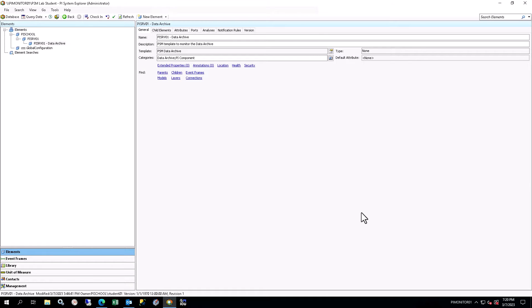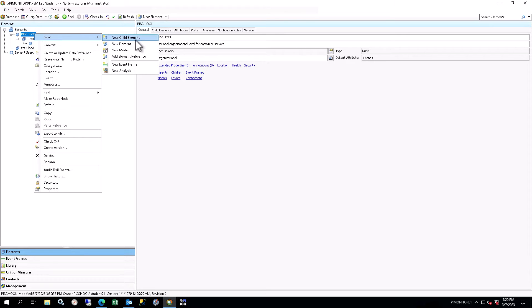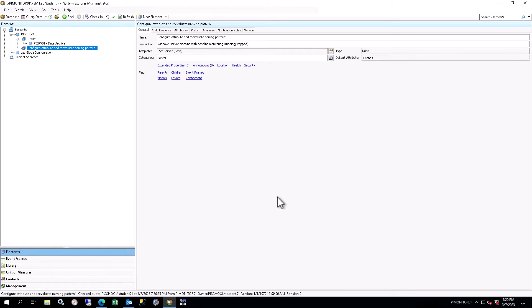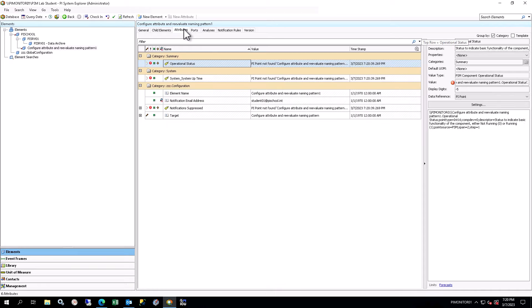In PI System Explorer, in the browser, right-click the PI School element in your database and select New, New Child Element. In the Choose Element Template window, ensure reference type Domain Server is chosen and select the PSM Server Basic template. You will see a new server element under PI School in the element structure. For now, we just need a server element to exist so we can create the interface component under it. The element will have a default name indicating that user input is required. Select the Attributes tab in the viewer. This element uses the same template as the PI SRV01 element that you created previously, so the attributes and analyses will be the same.